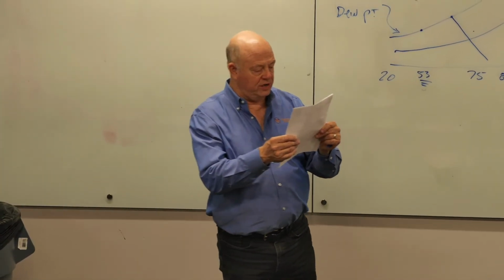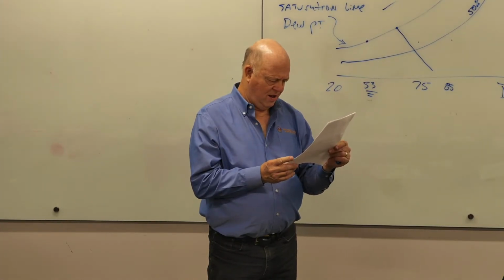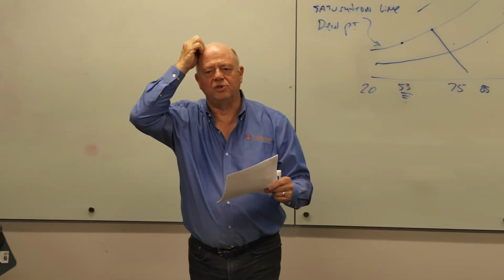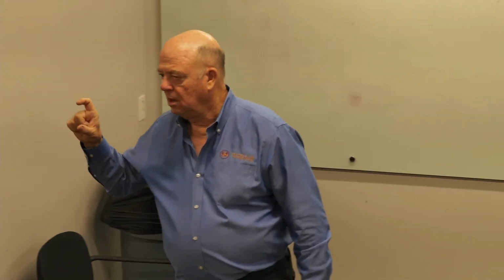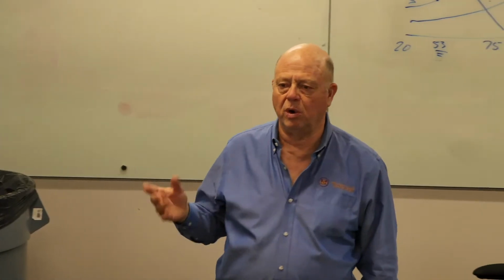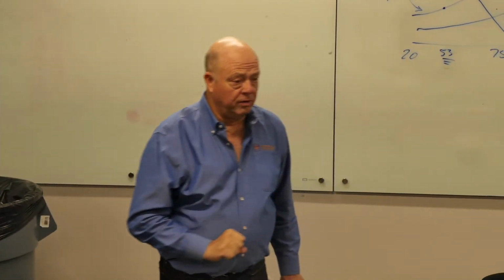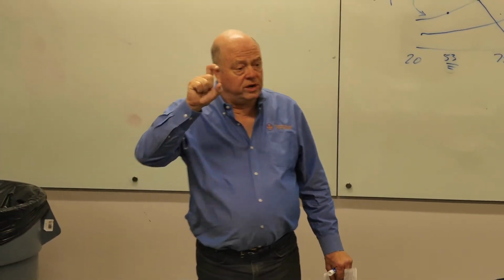So let's say we designed a surgery suite. This is really common. Let's talk about surgery suites for a minute. There's a code requirement for those. They don't care what temperature it is. Temperature's irrelevant. But you have to be between 20 and 60% relative humidity. The basis of that is that if you're drier than 20% relative humidity, the wound edges will dry out and it won't heal properly after it's stitched up or stuck together or whatever you're doing. The reason for the 60% is when you're above that, you are now at risk of a bacteria situation. Okay? So it's an infection control. So 20 to 60, and this is rigid.